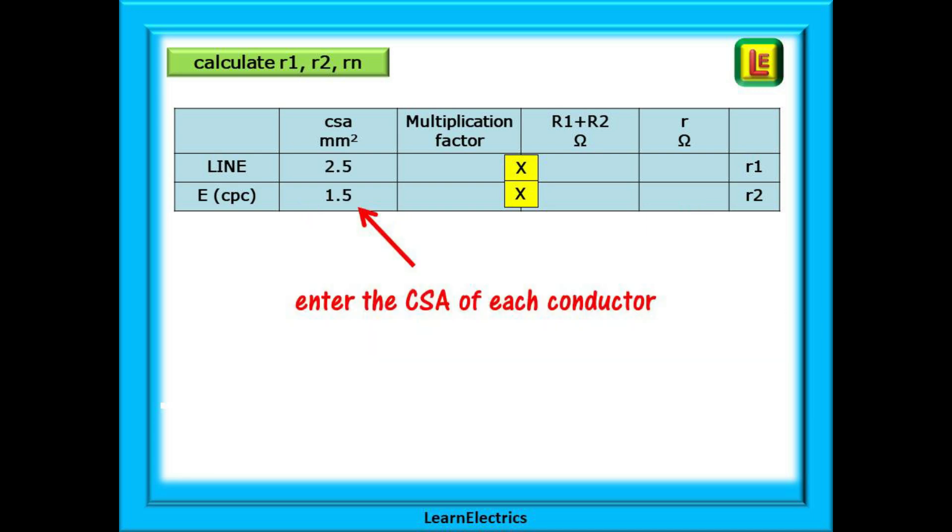So, put in the 2.5 for the CSA of the line and the 1.5 for the size of the CPC or Earth. Now, here's the trick.